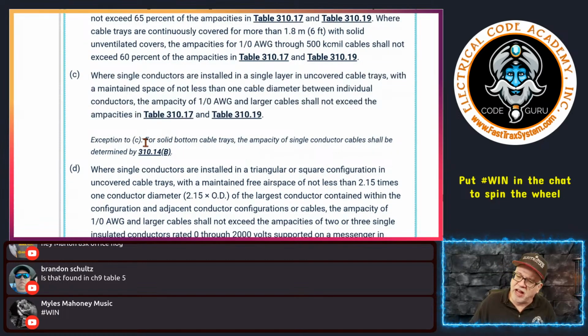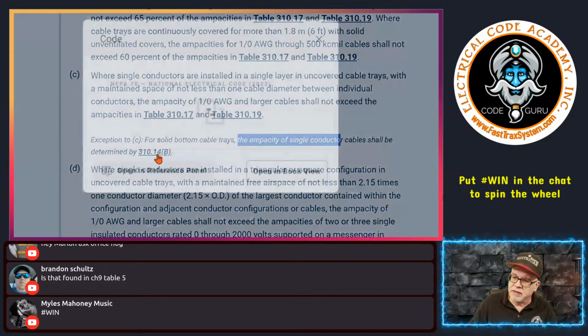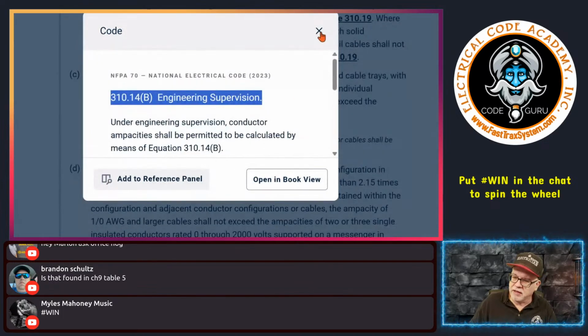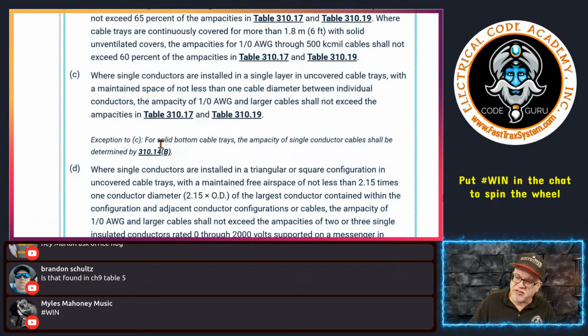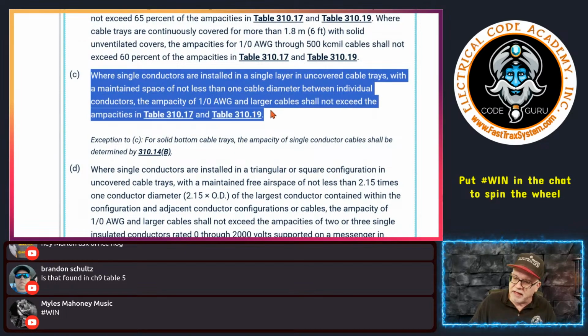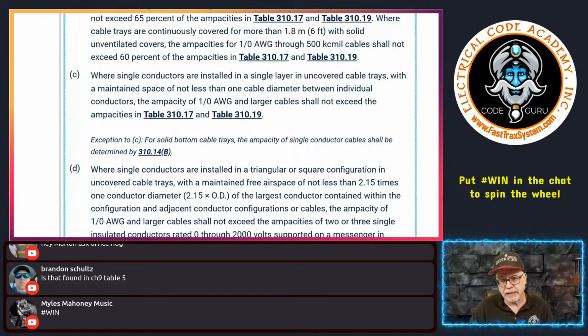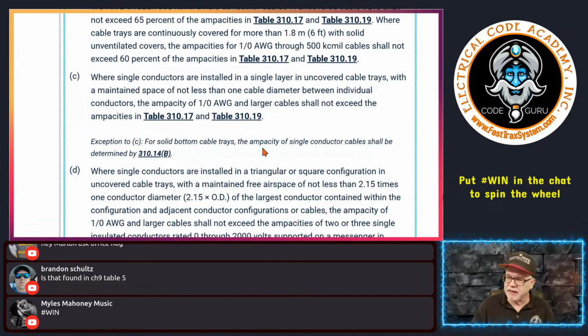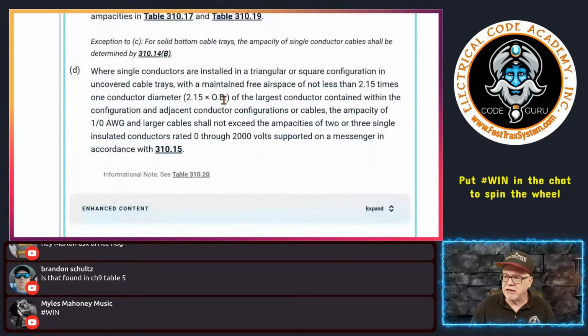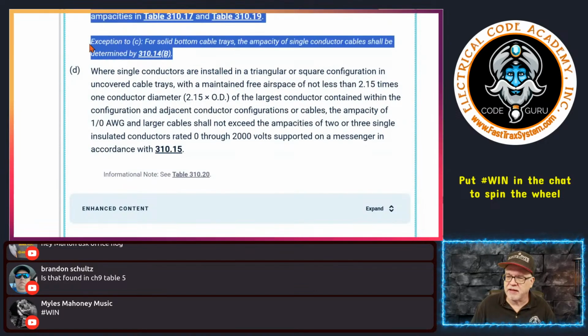However, it does say down here for solid bottom cable trays, the ampacities of single conductor cables shall be determined by 310.14(B). And again, that is engineering judgment, and they will use calculations, okay? So if you happen to have a solid bottom tray, then this right here can be a problem. If it's a solid bottom, the engineers will have to do a calculation for that, because you're not going to have the heat dissipation. It's solid bottom, it's going to hold the heat in, that type of thing. So this is going to impact the design of it.